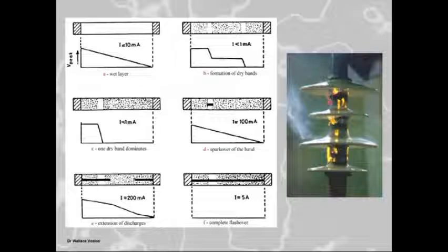So what does it do? It starts drying out the pollution layer here, and as it dries out the pollution layer, we get something we call a dry band. On that dry band, the earth potential transfers down to the dry band and the high voltage potential transfers up to the dry band, and you get dry band discharges and dry band sparking or arcing, depending on the current level. And then the resistance of this pollution layer will determine what current is flowing through that dry band discharge.